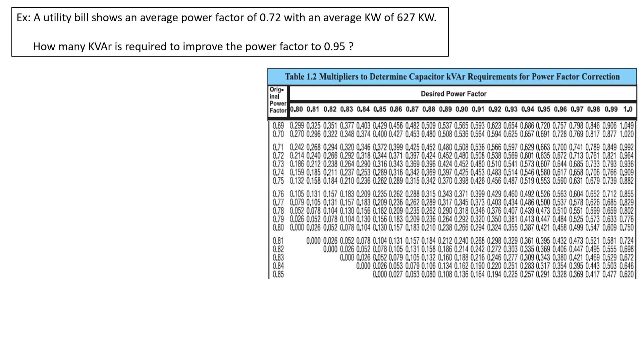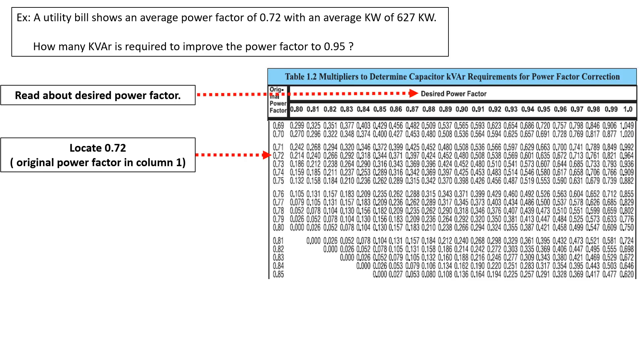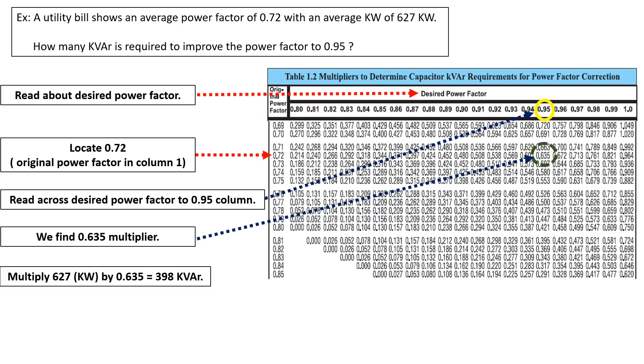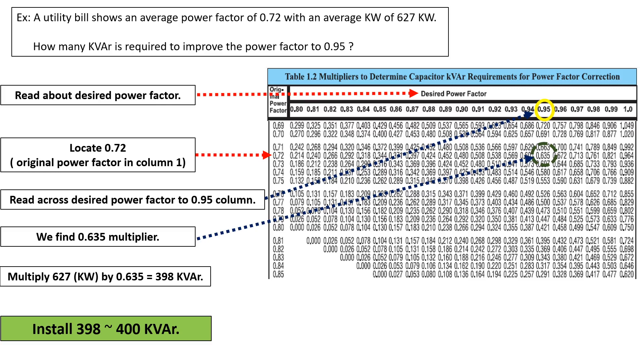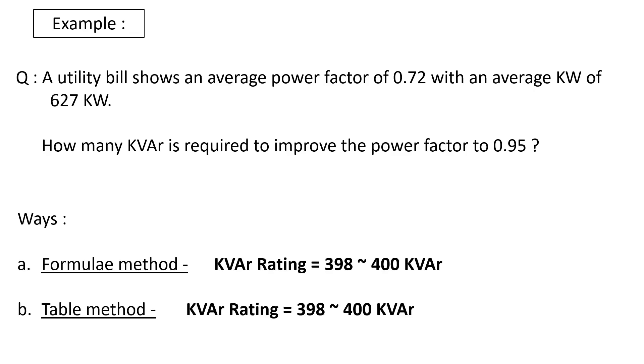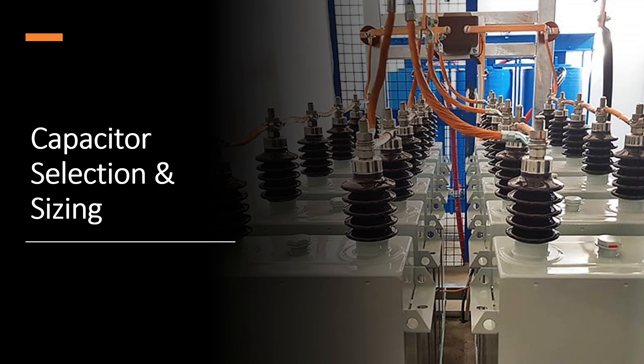Refer to the table — use the x-axis for present power factor and y-axis for required power factor. We get the multiplier as 0.635. Simply multiply this factor with the load in kilowatt to get the required kVAR. In this case we are getting 400 kVAR as the answer, confirming the result from the formula method.